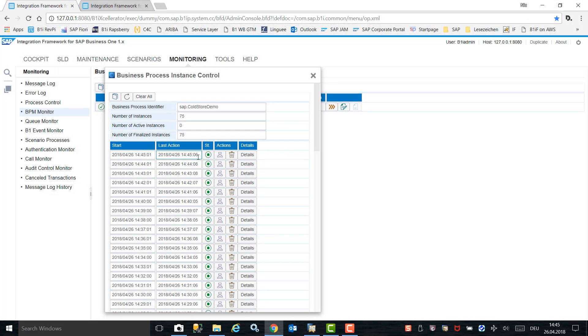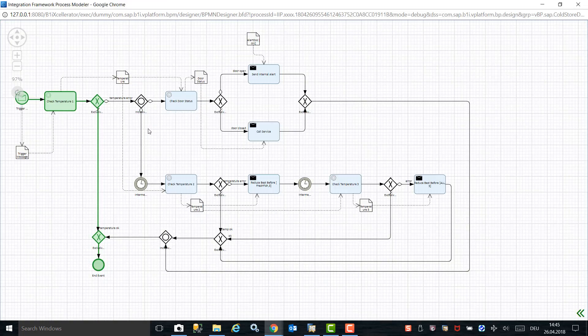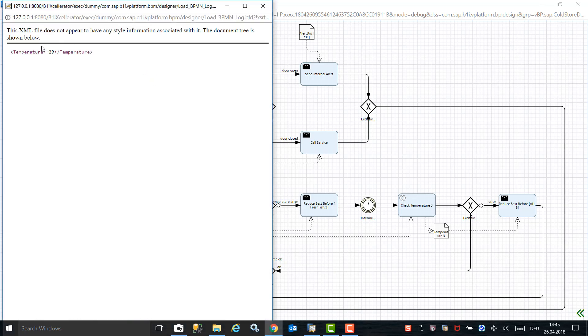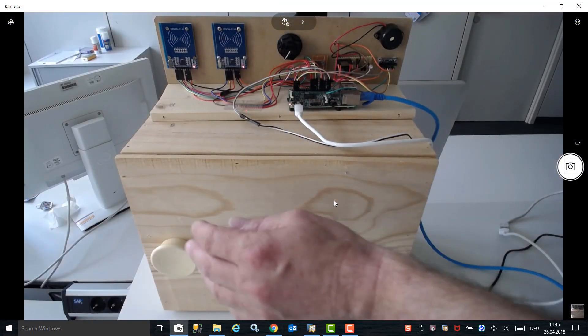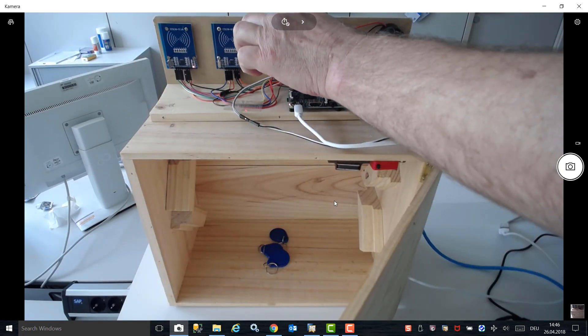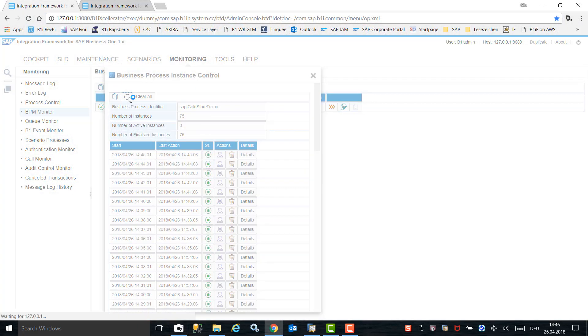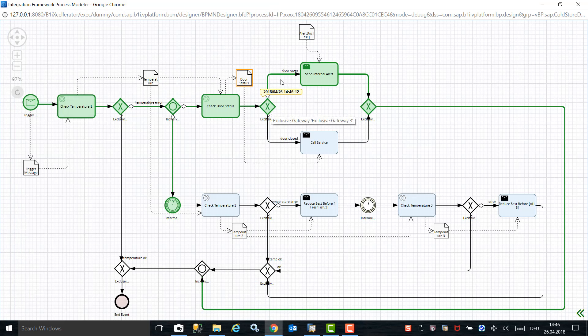In the Integration Framework, we can see that the scenario is running — every minute the instance runs and provides a result. From the Integration Framework, you can monitor the results by directly opening the Integration Framework process modeler. Everything is currently running fine, indicated in green, as the temperature remains at minus 20 degrees Celsius. Back in the cold storage unit, we open the door and increase the temperature to see what events are triggered. Drilling down into the check temperature step, we can see that the temperature is now minus 12, which is warmer than minus 18, and the check door status indicates that the door is open. This has triggered an alert in SAP Business One.